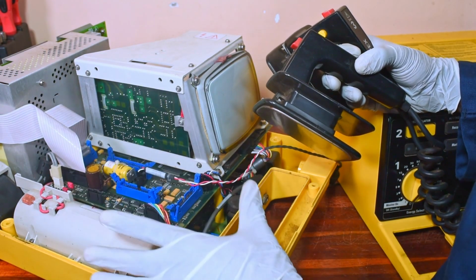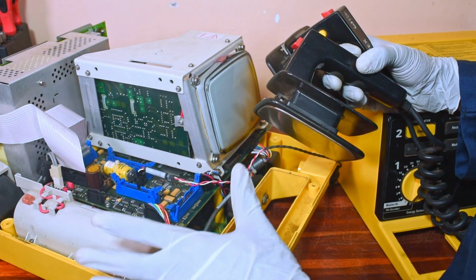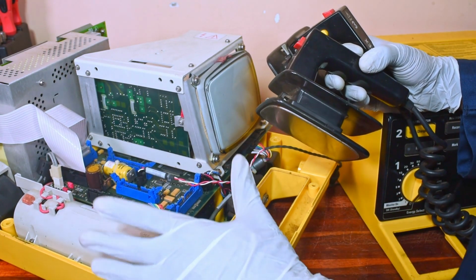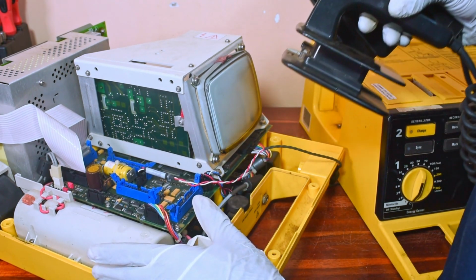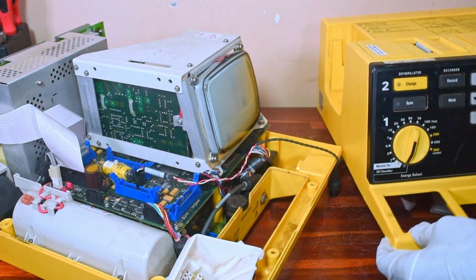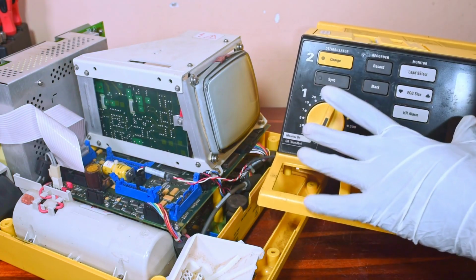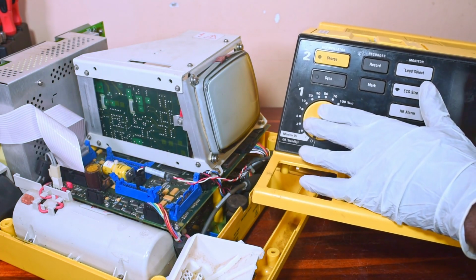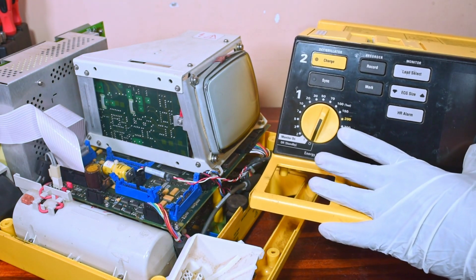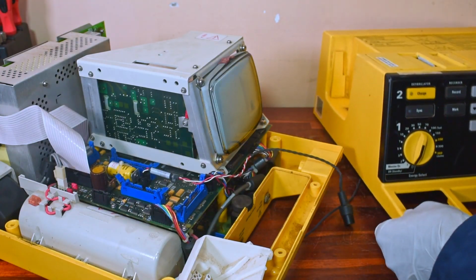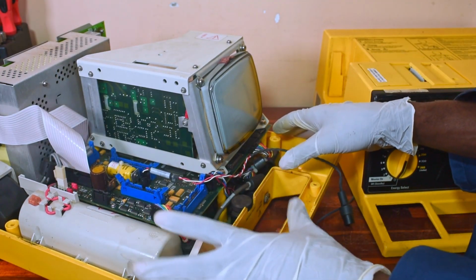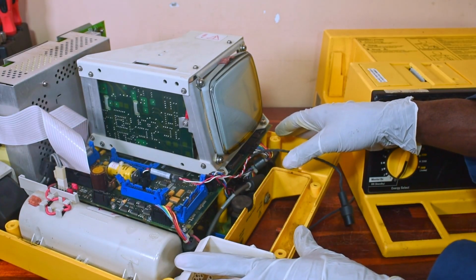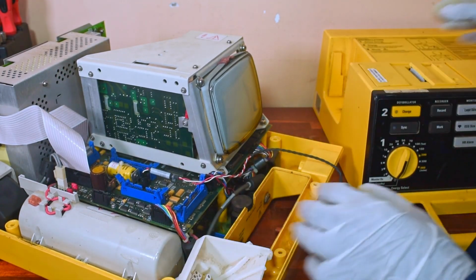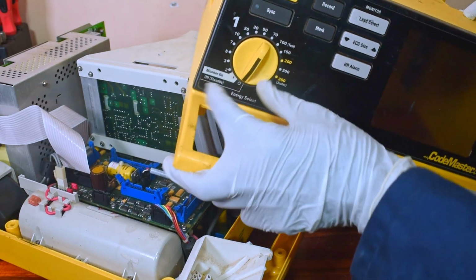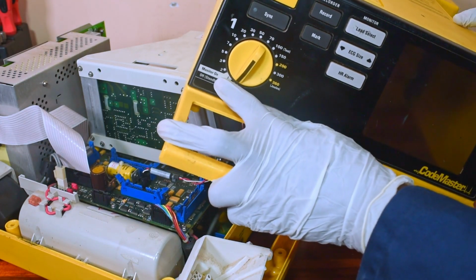If the device is in synchronization mode, the defibrillation energy is delivered only when the device detects the next R wave in the patient's heart rhythm. The defibrillator can be disarmed by turning the energy select control to the monitor on position. This device can also be used as a monitor for cardiac monitoring. For this mode, the energy select control should be turned to the monitor on position.